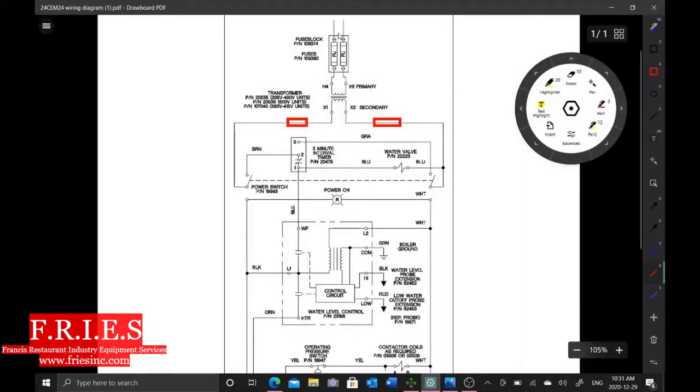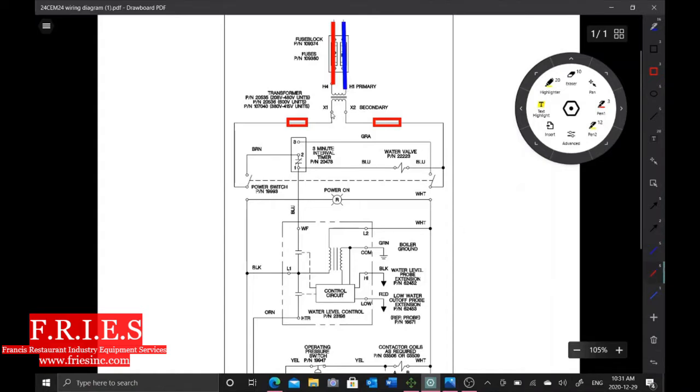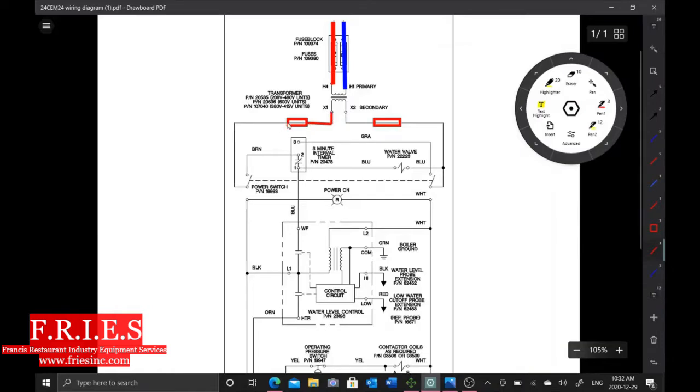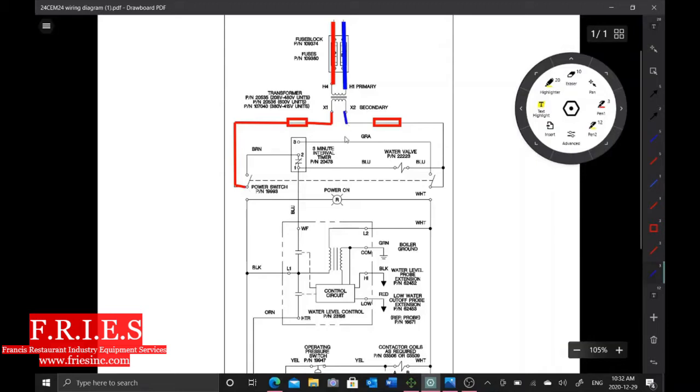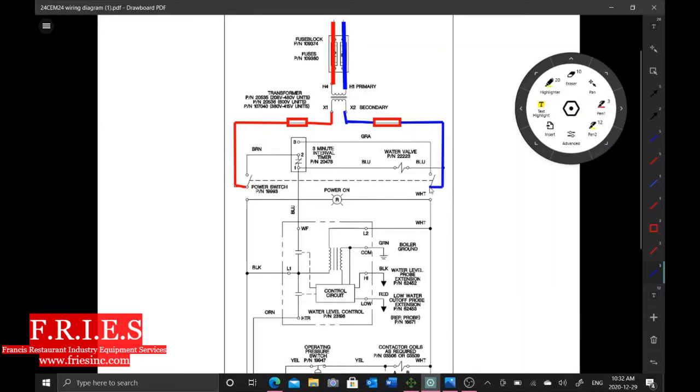All right, so we start through these fuses. We're coming at 600 volts L1 L2, and then we're coming out of our transformer at 120—in our case, it's actually 130. So we're coming out of our transformer here, we're going to call L1 our red side, we're coming to our power switch. Same thing's happening on the blue side, we're going to come through this temporary fuse that I installed, and we're going to come right down into this switch here. As soon as the switch is put in the on position, we're sending power down through here.